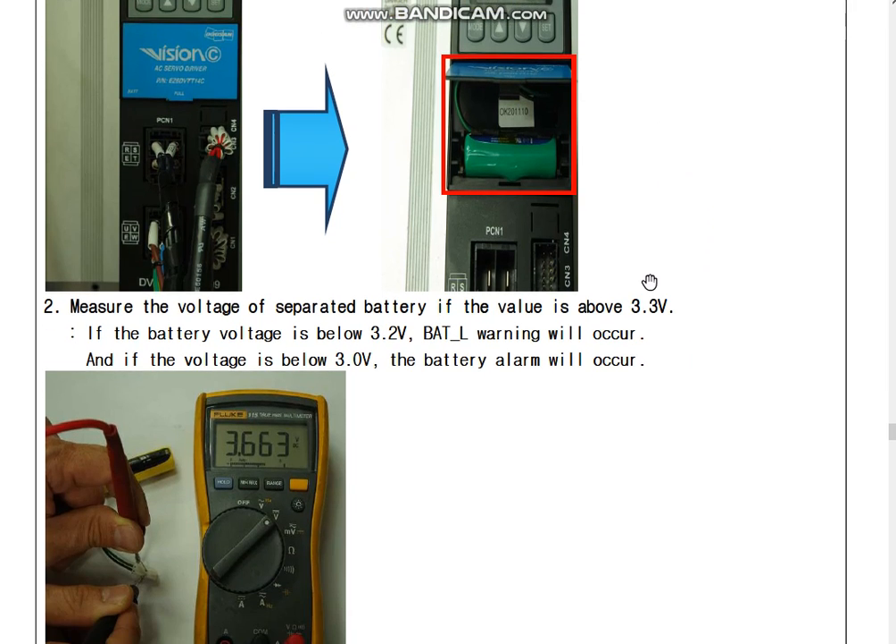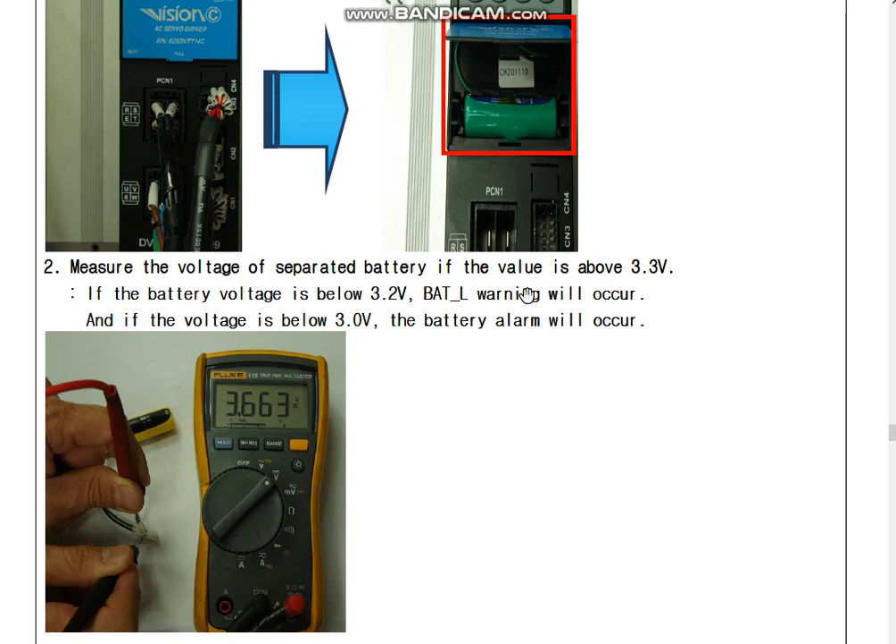Please measure the voltage of the separate battery. It should be above 3.3. If the battery voltage is below 3.2, a BAT_L warning will occur. If the voltage is below 3.0, the battery alarm will occur.